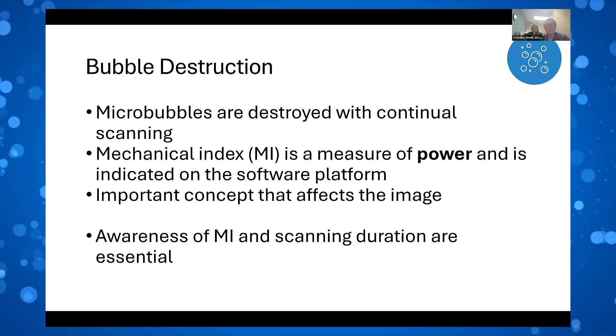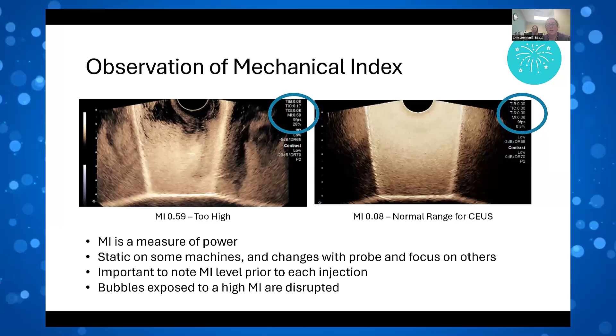So we're going to focus a little bit on the bubble properties and what happens when we destroy these microbubbles. So mechanical index, as we mentioned before, is a measure of power. It's static on some machines, and it changes with probe and focus on other machines. So it's important to note your mechanical index prior to each injection, before you do any kind of scanning, because bubbles exposed to a high mechanical index are disrupted.